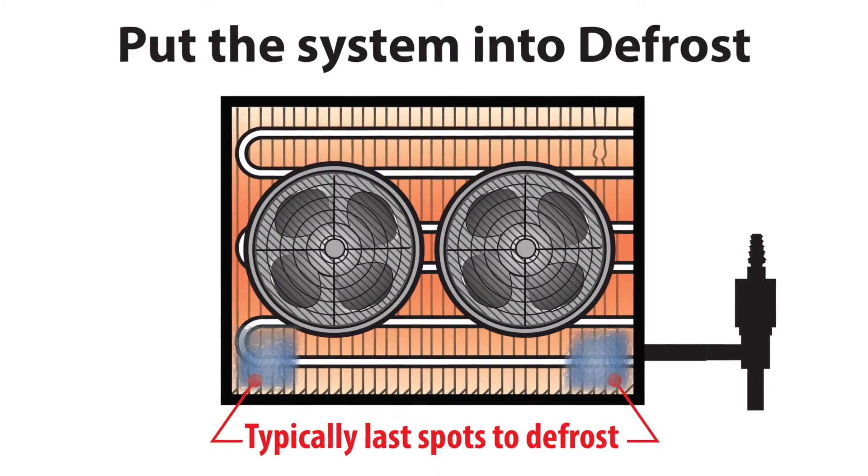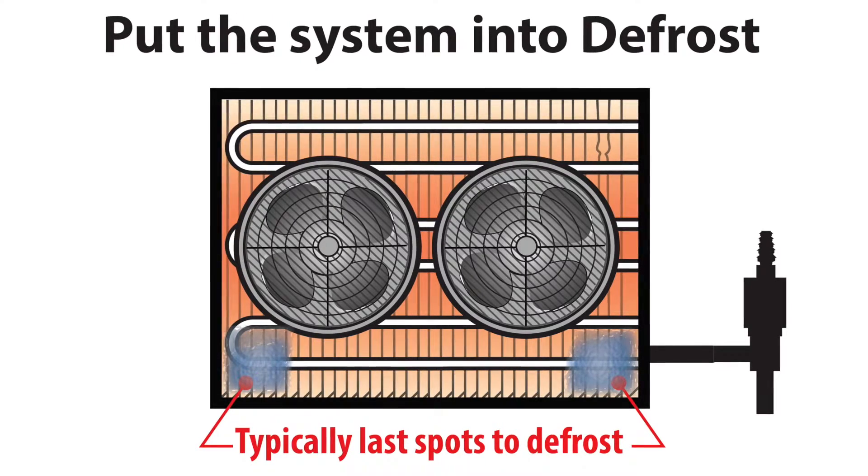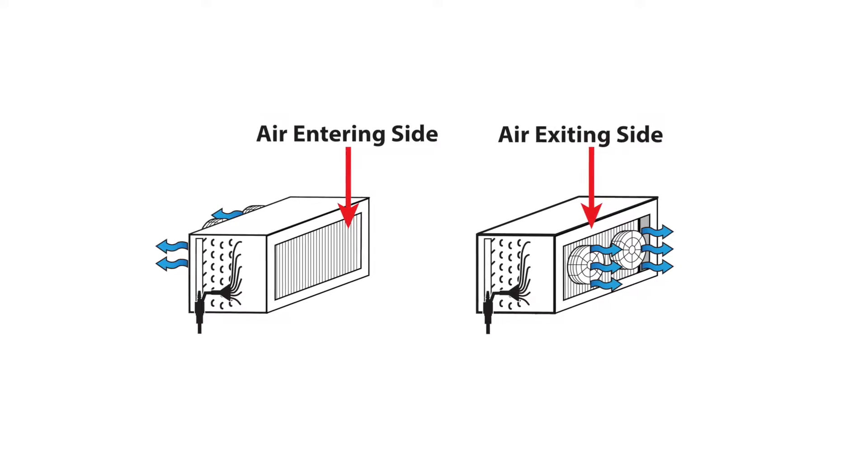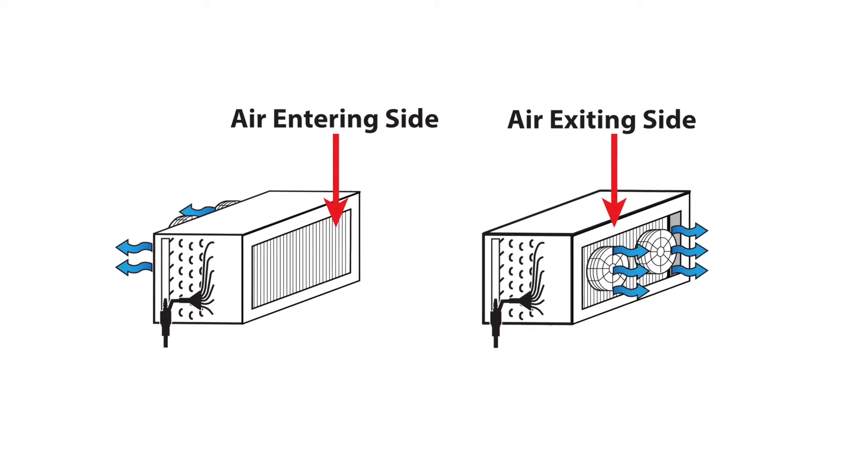Specifically, the last place frost disappears during the defrost cycle is the correct coil sensor location. When viewing the frost pattern, monitor both the air entering side as well as the air exiting side of the evaporator coil.